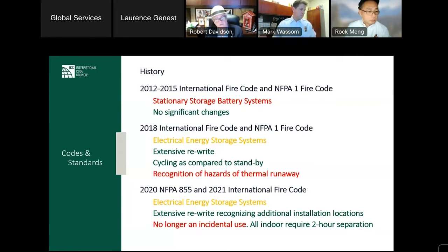One of the things we did in the building code era is it's no longer an incidental use. In other words, we got it out of that portion of the building code and simply required 2-hour separation. That got rid of that 10% limit, but it formalized a 2-hour separation where in the past it was 1 hour, 2 hour, depending on occupancies. And the 2021 fire code got rewritten and pretty much matches everything that's in the 2020 NFPA 855. Again, because we're trying to keep consistency.